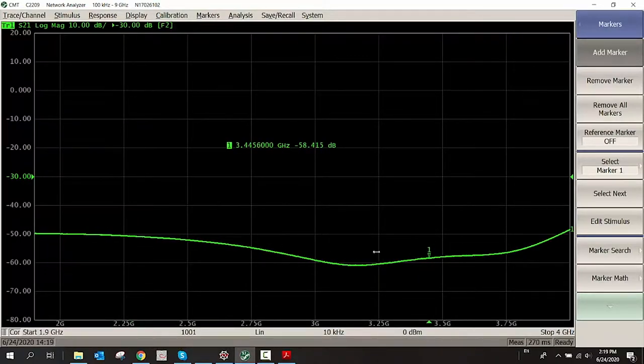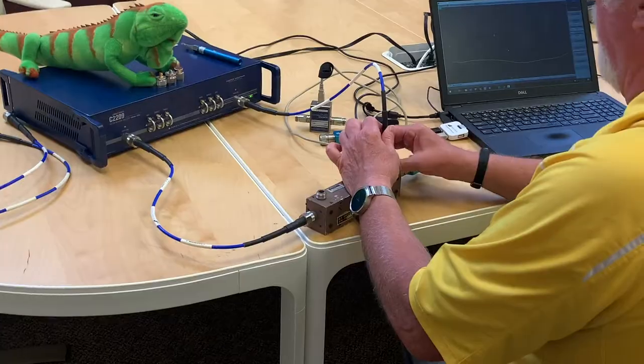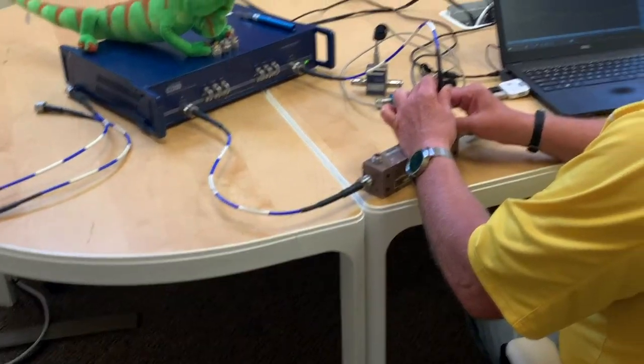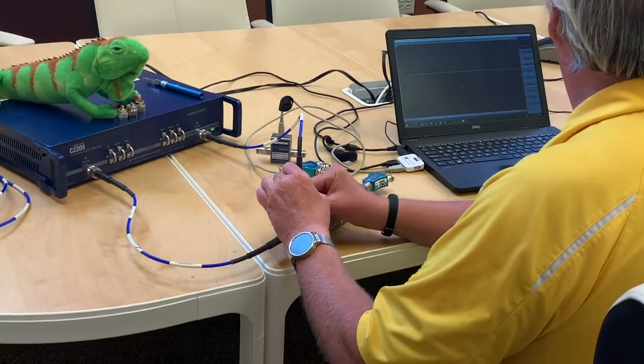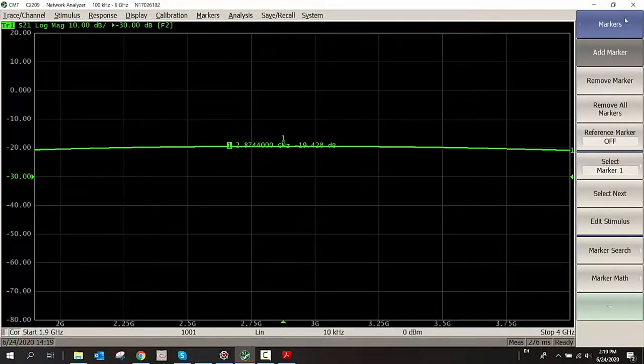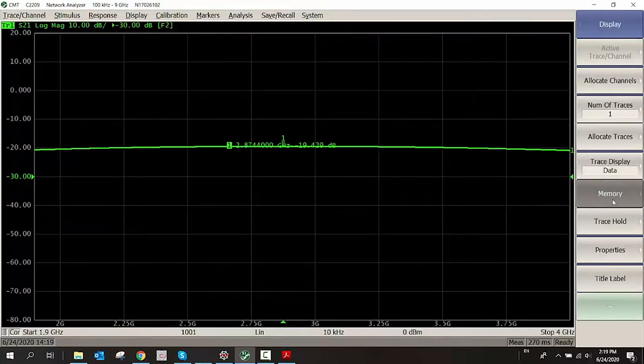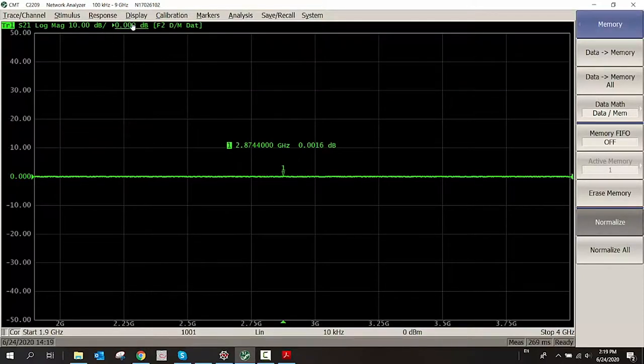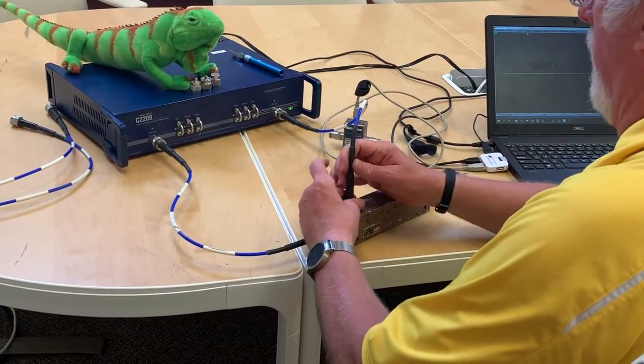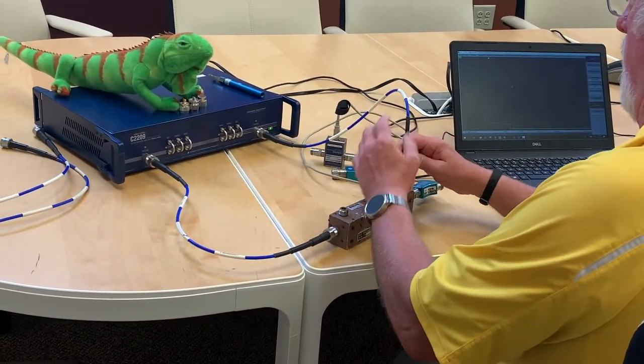So now you can see that I do have an error signal. It's minus 58 or 60 here. So what's important to note though is that there is a coupling loss of this coupler to begin with. So you need to subtract the 20 dB from this. What I should do is this. Let's assume for the moment that this coupler is symmetrical. It's a pretty safe bet. And I will go to memory and normalize. And now I've removed the coupling so it measures zero.